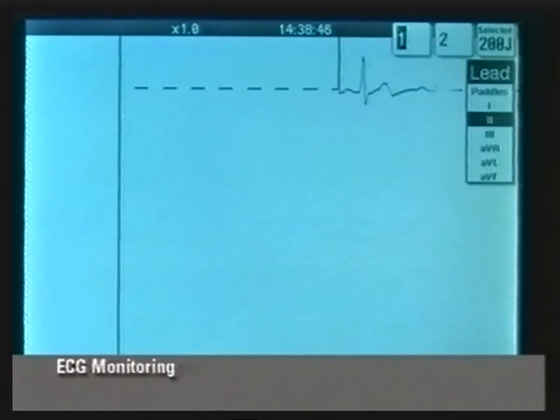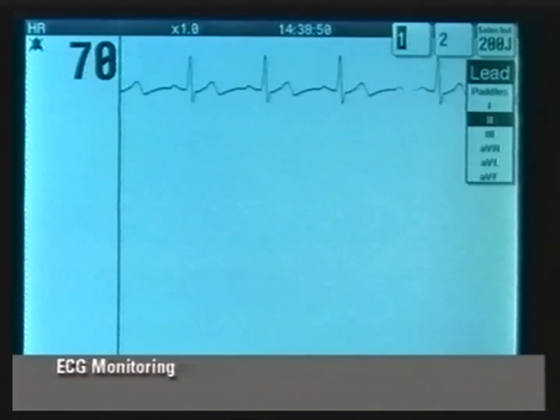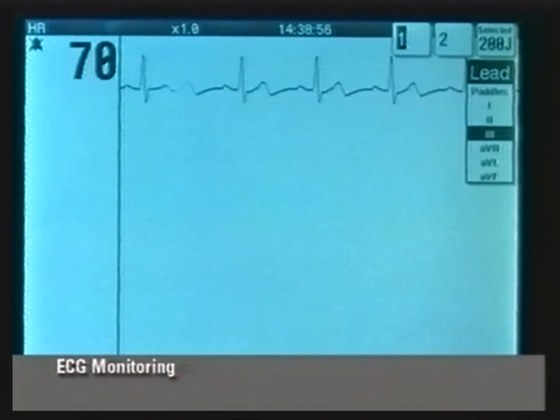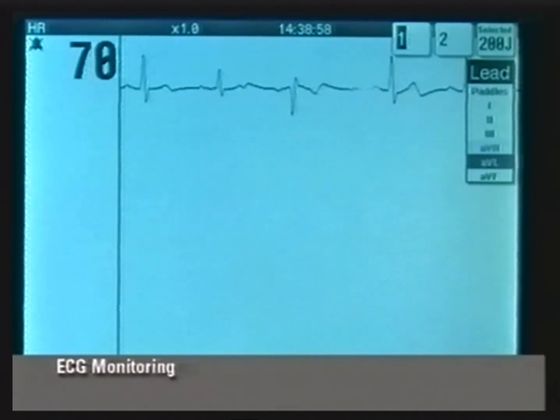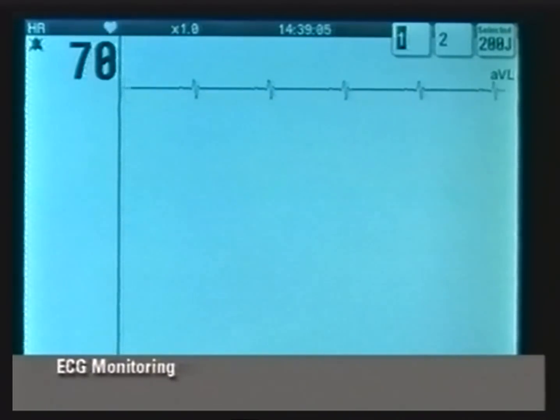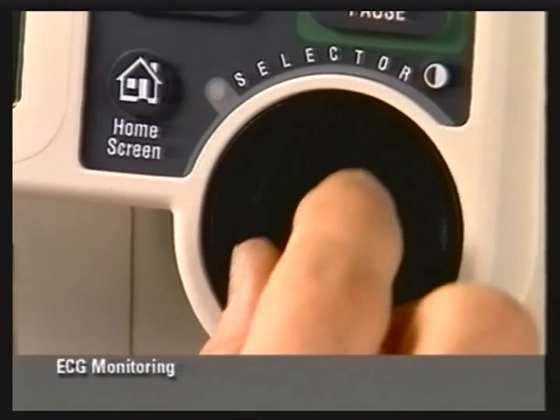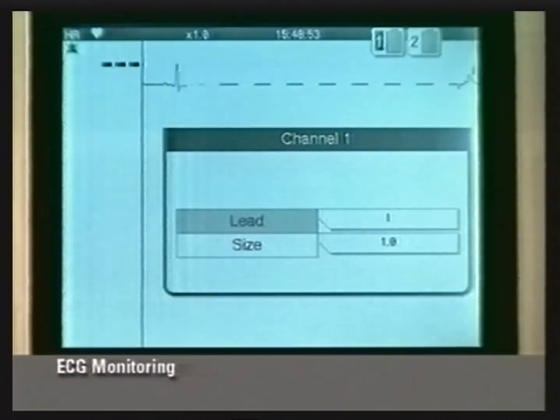The ECG lead menu appears and the lead automatically changes to lead 2. If another lead is desired, continue to press the lead button or rotate the selector. After a few seconds, the menu disappears, or you can press the home screen button. Alternatively, you can use the selector to highlight channel 1 and change the lead.